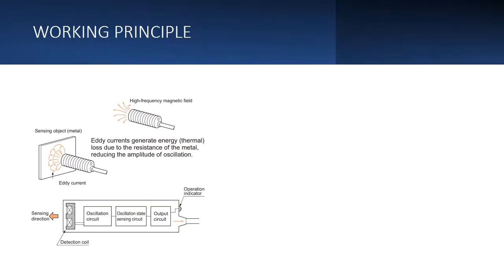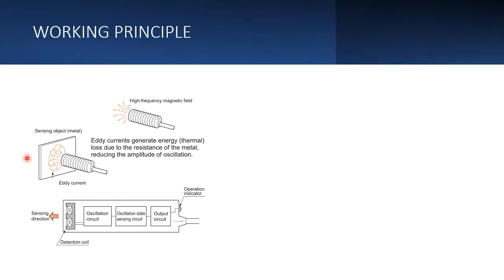Let's get started with the basic working principle — we won't deep dive into the electronics, but we should know the basics. A sensor is given an electric supply which creates a high frequency magnetic field. When a metal object is in the proximity of the sensor, it creates eddy currents in the conductive material. The important point is that eddy currents are generated in conductive materials only.